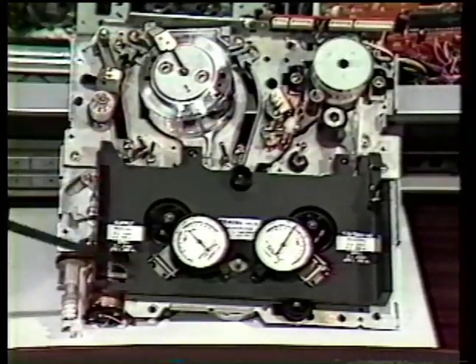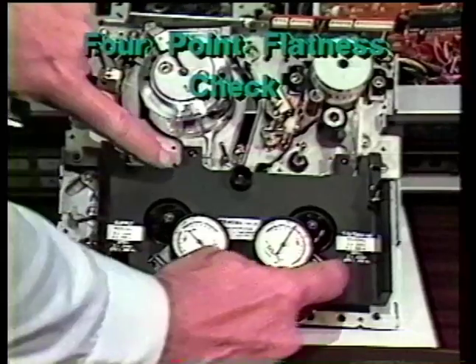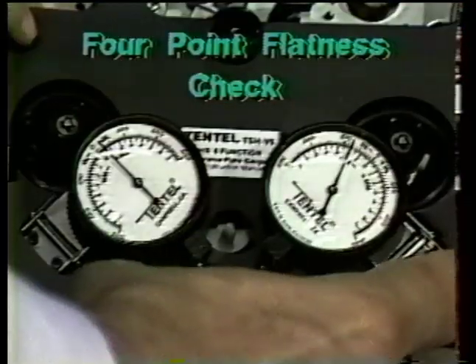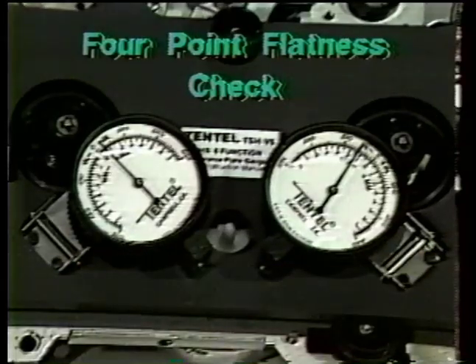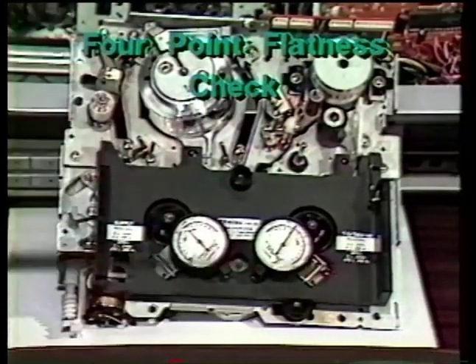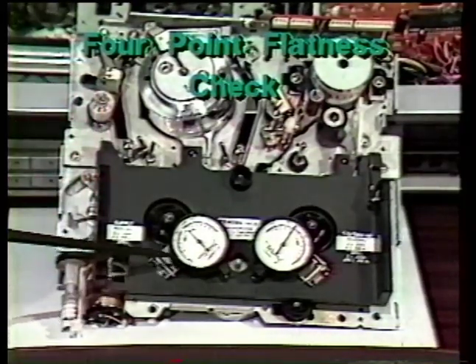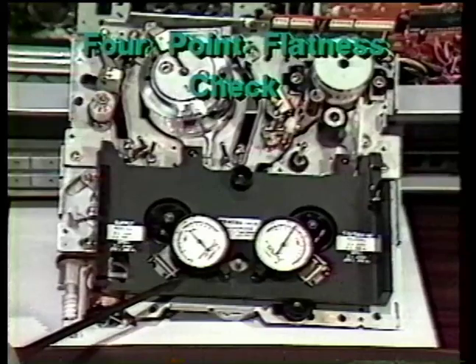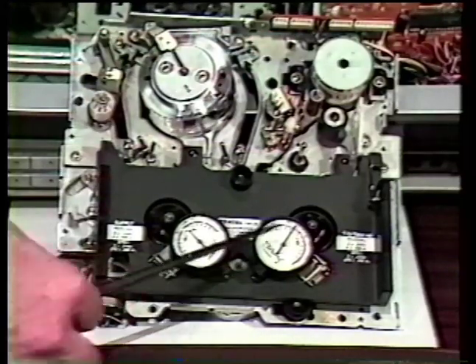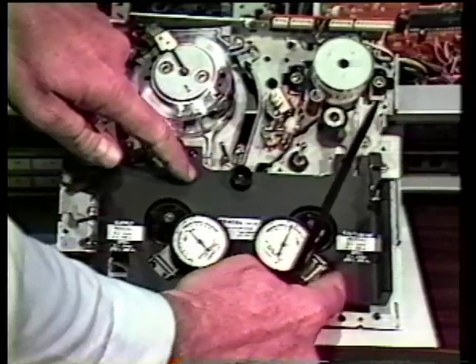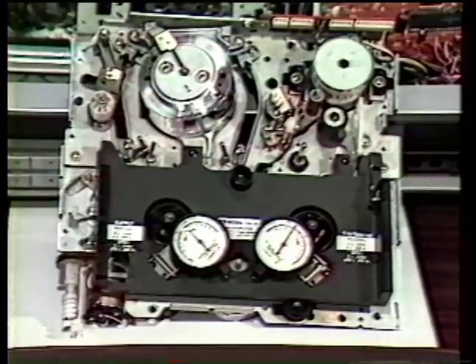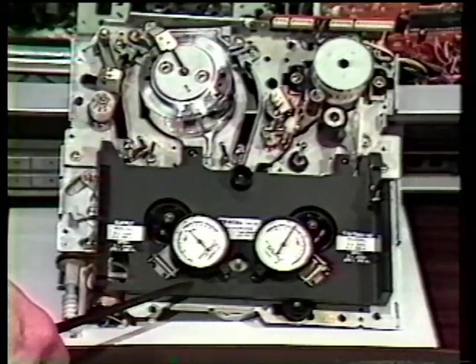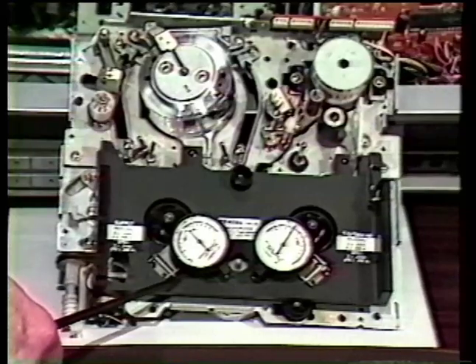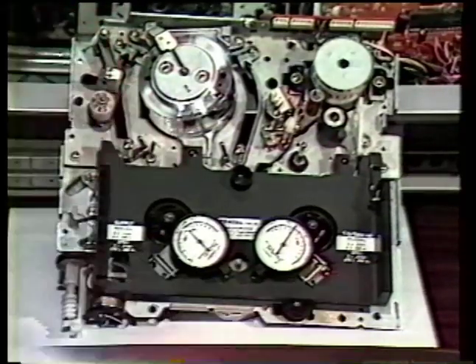Okay, the 4 points that we described, if those are not in the same plane, we'll notice rocking motion. You can see it there on this indicator. As we try to move it in this direction, we see no rocking. So in this direction, what it indicates is that, just like a chair having one leg too long or too short, you get a rocking. The direction that this is rocking now would indicate that this post is either too high or this post is too low. It's easier to make a post lower typically, so we would either Dremel, if this was significant beyond about 3 or 4 thousandths of an inch, which is about what it's at, so it's real marginal as far as repairing. But we would Dremel or file, or hopefully an adjustment screw, for adjusting this post slightly lower so that it wouldn't have that rocking problem.